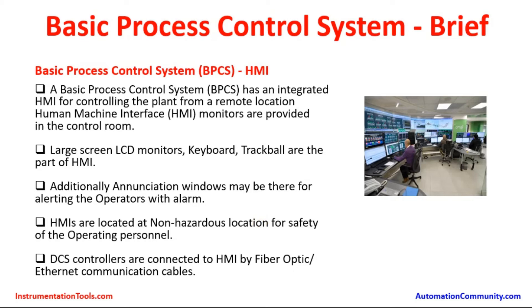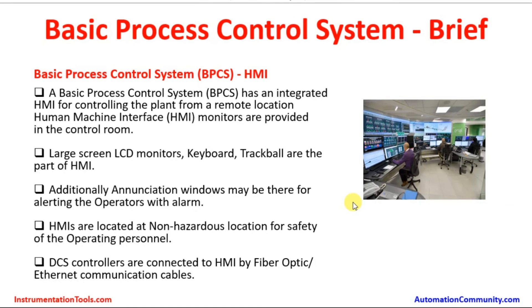HMIs are located in a non-hazardous location for safety of the operating personnel. In process plants like oil and gas plants, refineries, and other petrochemical plants, the process area contains a lot of hydrocarbons, flammable liquids, and highly toxic chemicals which are hazardous in nature. The operations personnel cannot be in that hazardous area, so they are located away from the process area and connected by fiber optic cabling. DCS controllers are connected to the HMI by fiber optic and Ethernet communication cables, with cables running from the field to the controller and then from the controller to the HMI stations.